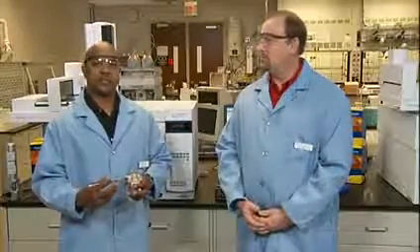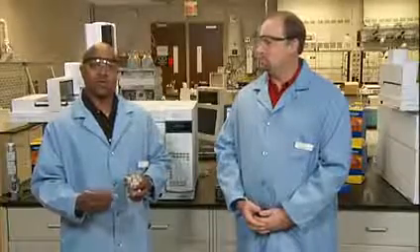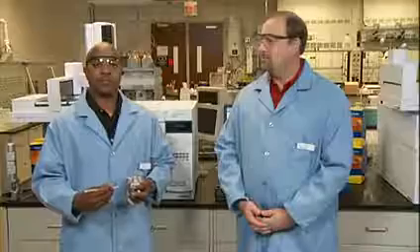The weldment assembly can be cleaned or replaced, especially if you're running pesticides or semi-volatiles. You may find some residual material coats the weldment. You want to clean it to minimize the inlet activity. You don't have to remove the inlet to clean it. I just removed it for this example.